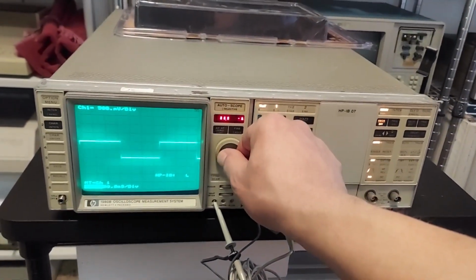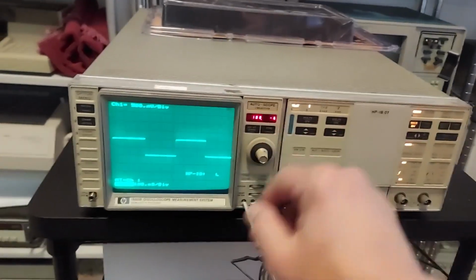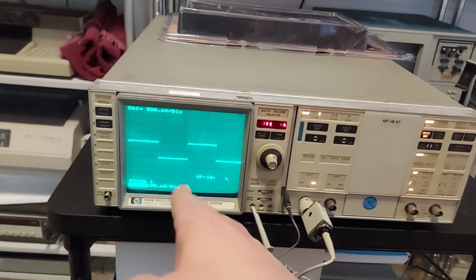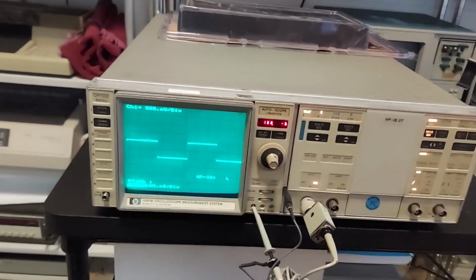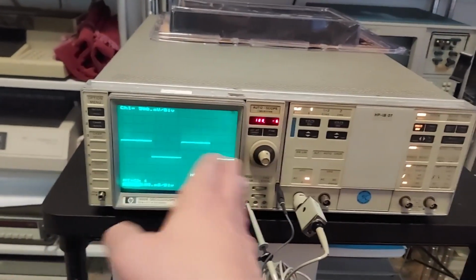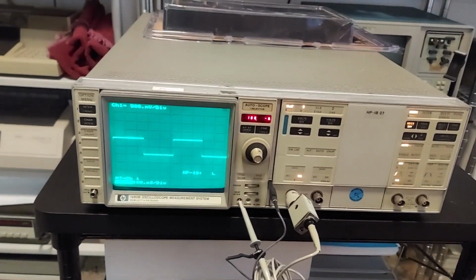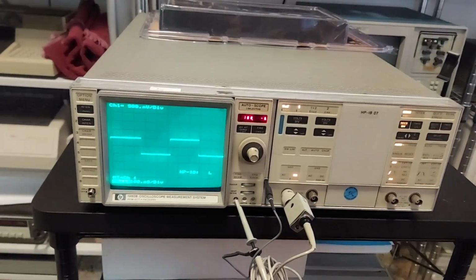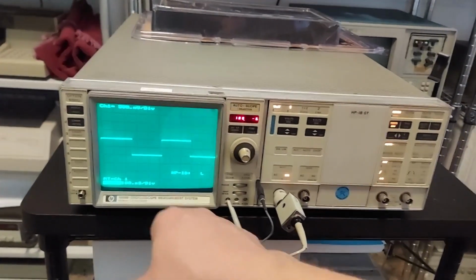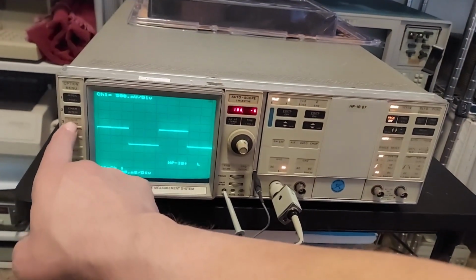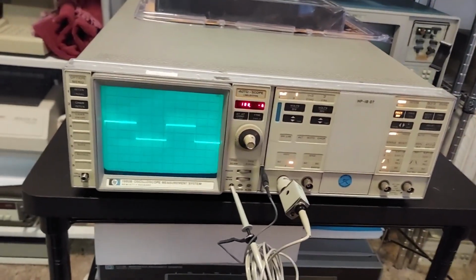And depending on what the trace speed is, I don't know if you can see this on the video, but there's a kind of an artifact scrolling sideways across here at the trace. It's caused by the chopping frequency of the readouts and the main trace, but you can always get rid of that by turning the characters off.